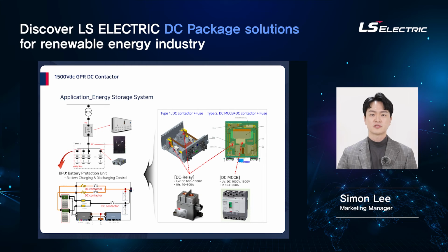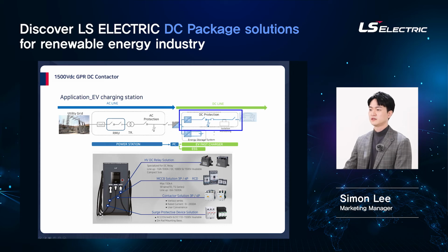In terms of energy storage system application, this contactor is commonly used in primary protection stage, which is called BPU, battery protection unit. Since it is crucial DC components together with fuse for protecting one battery rack, the capability of high ampere making, breaking, and arc extinction would be highly required. Also, our DC contactors are widely installed in DC EV chargers. As the capacity of EV charger increased upon request for less time for charging, we believe that there must be demands for high capacity of DC contactor in near future.